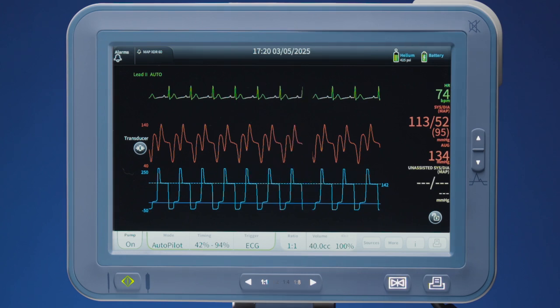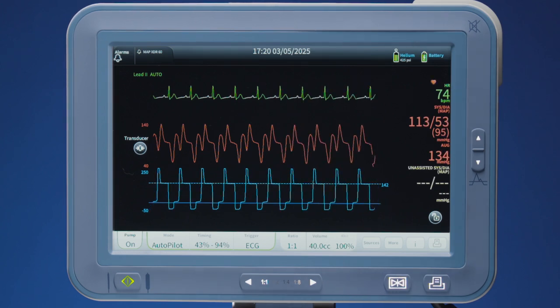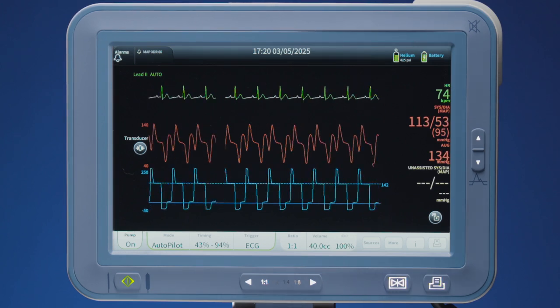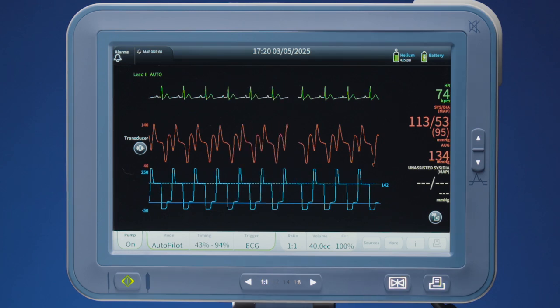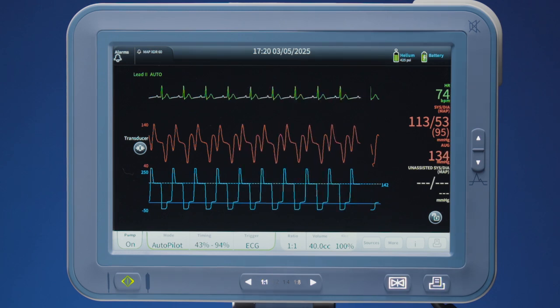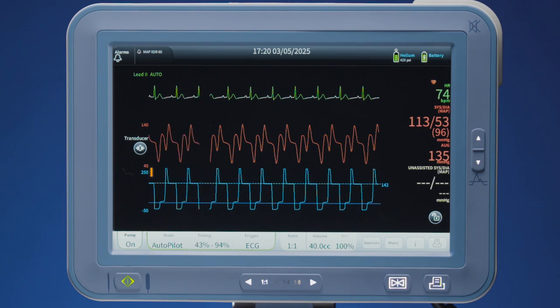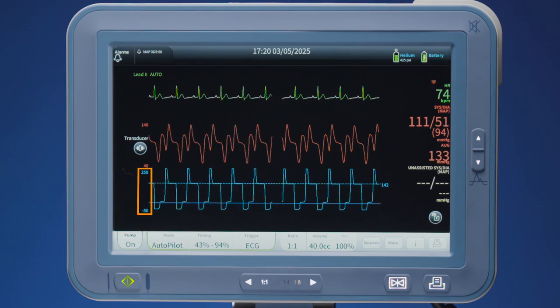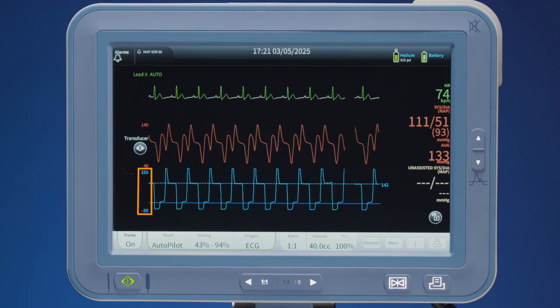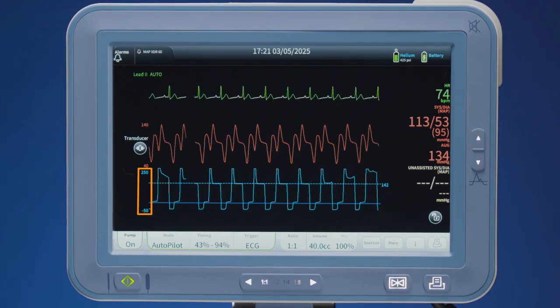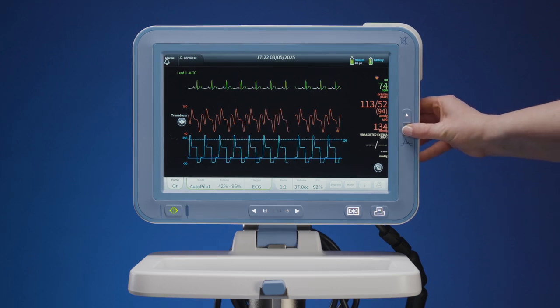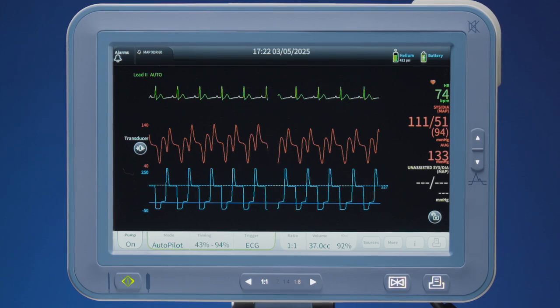The balloon pressure waveform is shown in blue. The goal is for the intra-aortic balloon to be 90 to 95% occlusive of the descending thoracic aorta. The scale for the balloon pressure waveform is shown to the left of the balloon pressure waveform and is a fixed scale of -50 to +250 millimeters of mercury. The balloon pressure waveform, BPW, represents helium movement between the console and the IAB catheter. It is a calibrated, continuous waveform allowing objective assessment of the safety and effectiveness of counterpulsation.